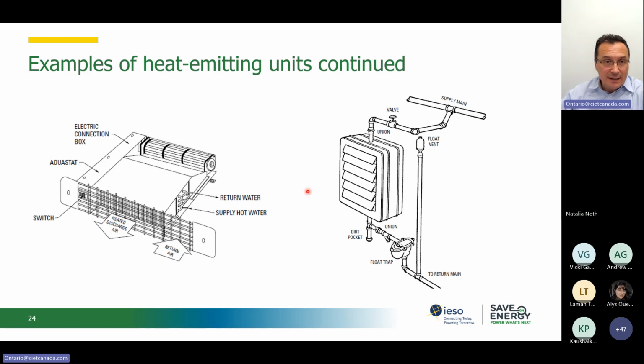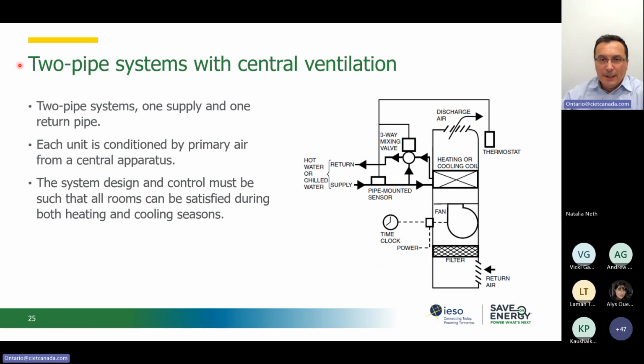If we look at how we transfer heat inside the units, we have options based on when we require heating or when we require cooling. Very popular in multi-residential buildings that have individual unit control for the heat delivered to the space. We have two-pipe systems. And in that case, the changeover happens in the central plant location. We switch from cooling to heating based on the period of the year. In many cases, we have regulations that ask building operators to provide heating at a certain time of the year. And inside the unit, we just control how much heat we take over from this central system, from the distribution loop, and distribute it in the space. And in this case, we use a fan to distribute the heat in the space.